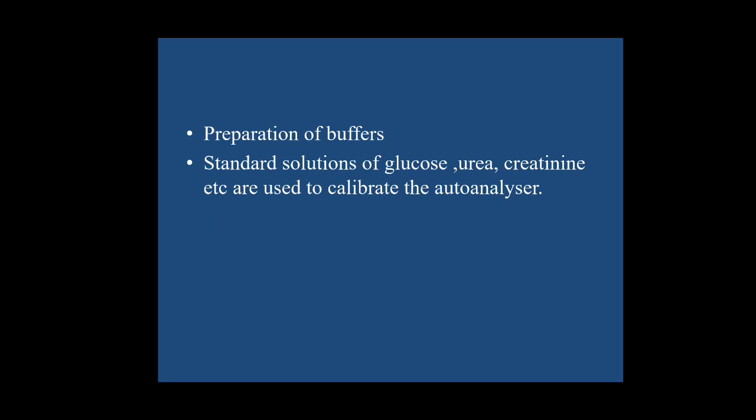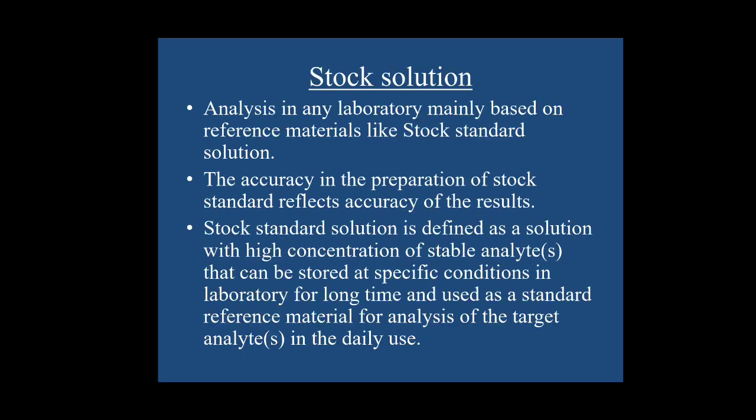We will know what concentration the standard is. If the instrument is giving the same value, then the instrument is correct. If it is not giving the proper value, then there is some problem with the auto analyzer. So that is how we use standard solution in auto analyzers. Next, coming to stock solution.